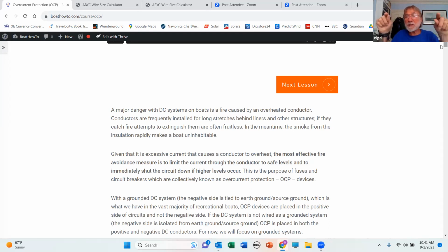You go to the ampacity side of it. You put in there the conductor size. You put in there the insulation temperature rating. You put in there whether or not it's in a hot ambient environment. You put in there if it's bundled. And then it'll tell you what the maximum number of amps are that you can put through that particular conductor. That tells you the maximum amp rating you can have for a fuse or circuit breaker.